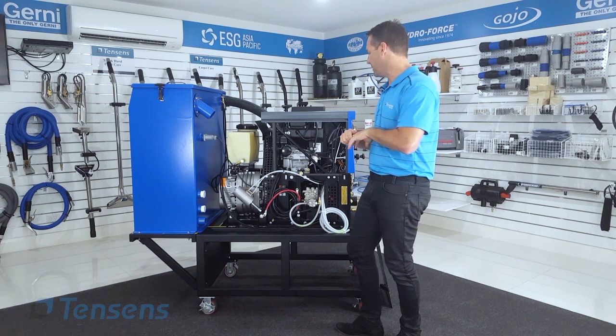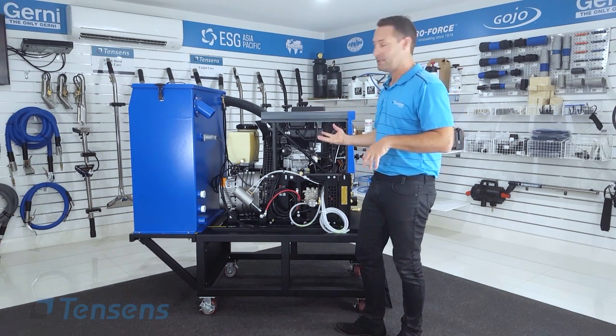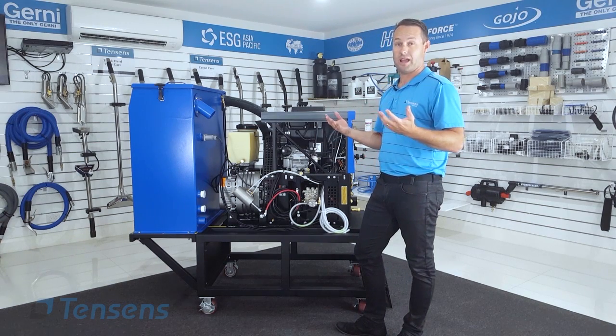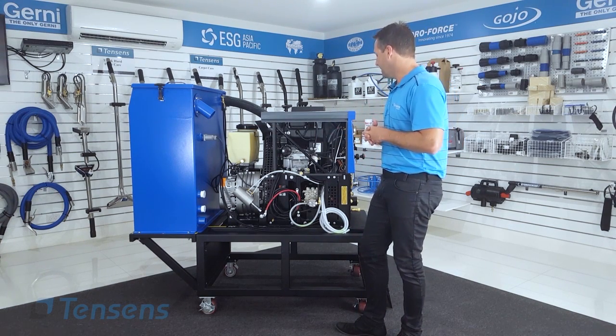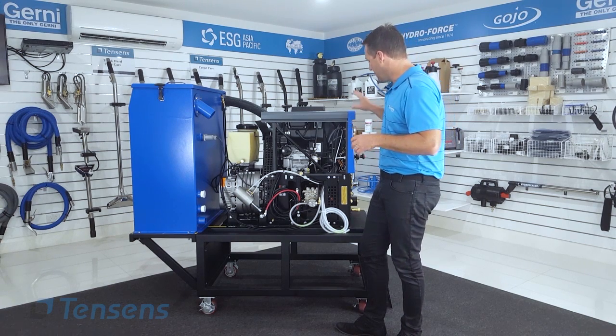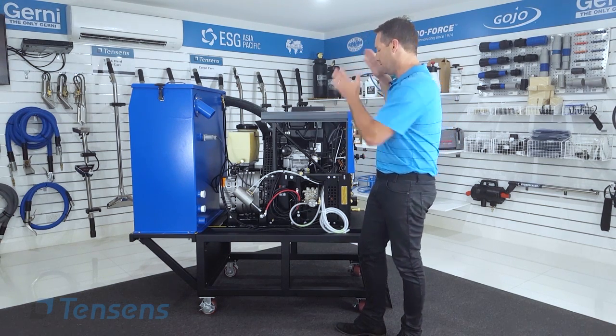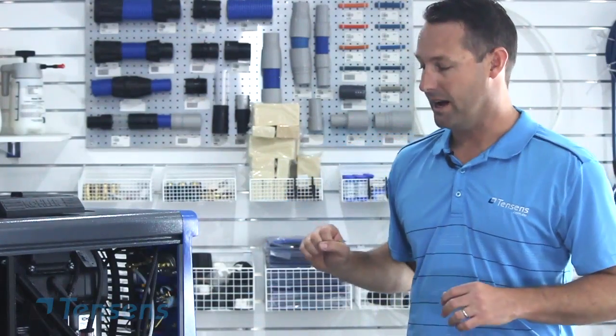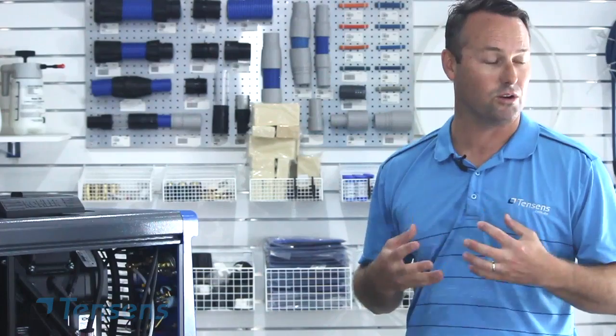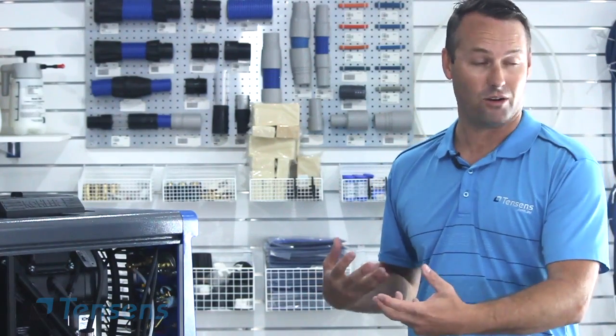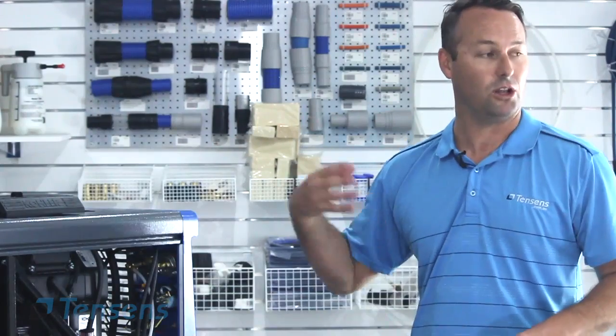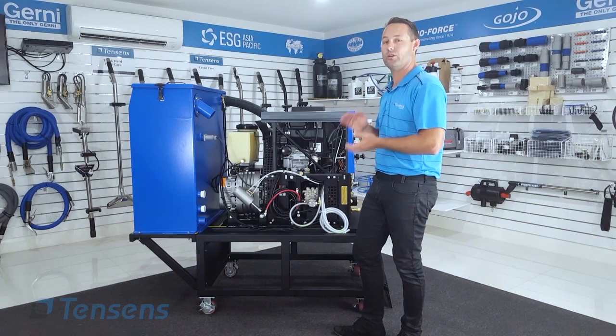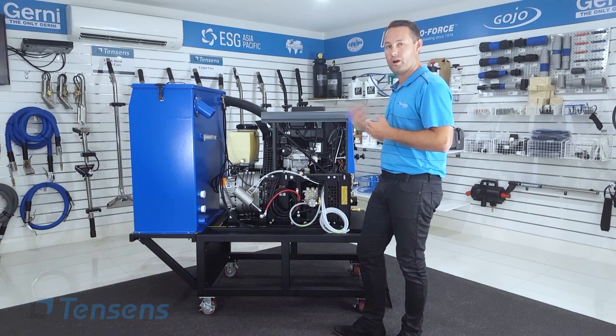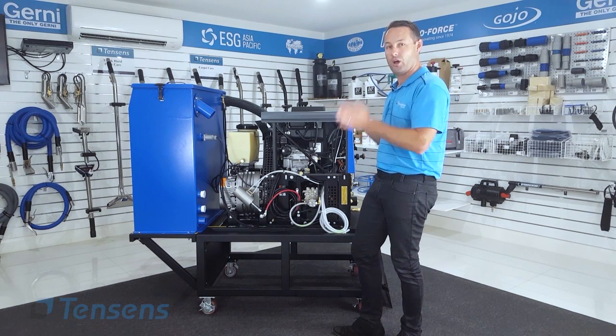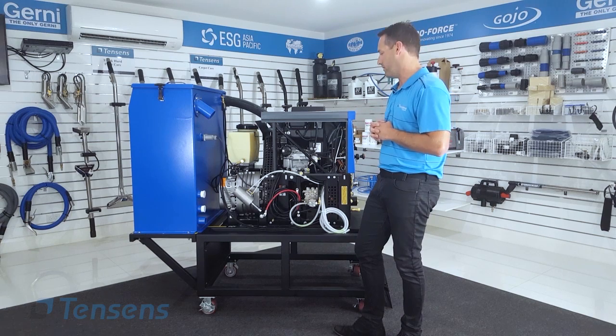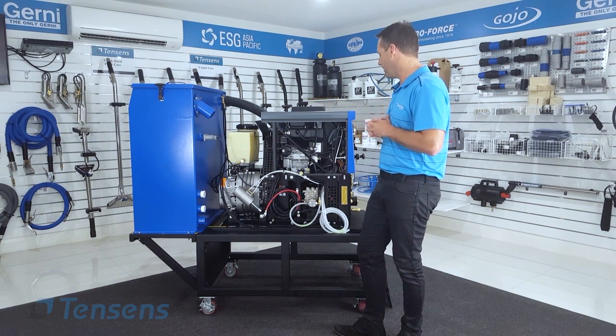In the 500 hour, we're talking adjusting and checking belts, we're not replacing. We can go well over 1,000 hours on a belt quite comfortably. The belts themselves are match perfect belts, so they're specially designed, perfectly the same size. These belts last a long, long time. The reason why they last so much longer than others is the length of the belt. It's got a lot of cooling around the belt. A short belt doesn't get a lot of time to cool off. When you're not cooling off a belt, it overheats. Adjustment and alignment is very important with the belt as well. That's where you get wear and tear. So these are the things you check at your 500-hour service.